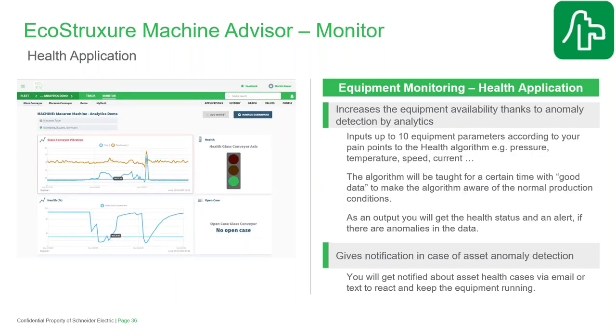Another piece that is part of what this does is the health. In the monitoring, we can do a health application. And what this really gets to is the idea of beginning to learn what the machine does. This is using machine learning and AI to understand what a good condition is and to understand when the pump is starting to move out of a good condition, and then notify you of that. So it's a step ahead of just basic analytics of good versus bad, because it's actually learning over time what's good and what's bad, and then being able to alert on a bad situation.